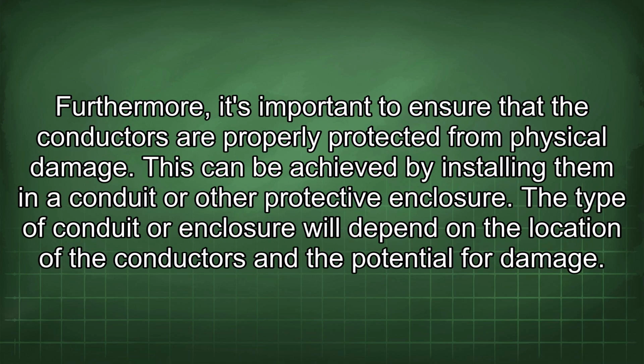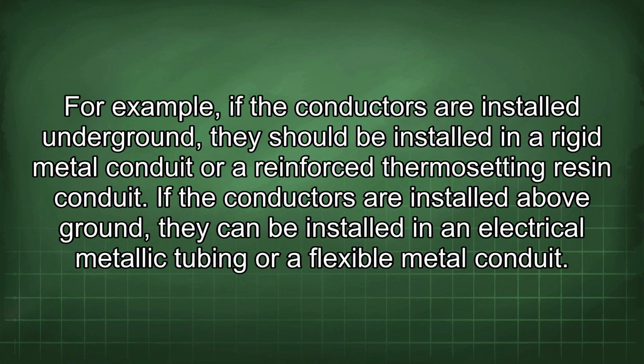Furthermore, it's important to ensure that the conductors are properly protected from physical damage. This can be achieved by installing them in a conduit or other protective enclosure. The type of conduit or enclosure will depend on the location of the conductors and the potential for damage. For example, if the conductors are installed underground, they should be installed in a rigid metal conduit or a reinforced thermosetting resin conduit. If the conductors are installed above ground, they can be installed in an electrical metallic tubing or a flexible metal conduit.